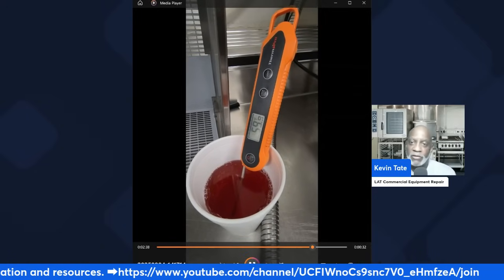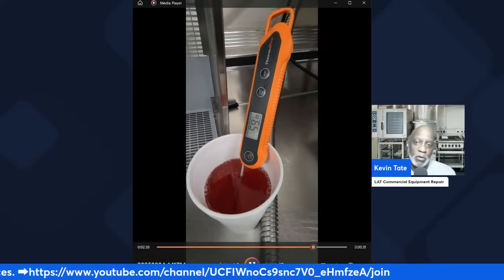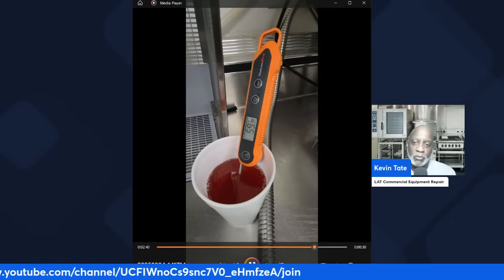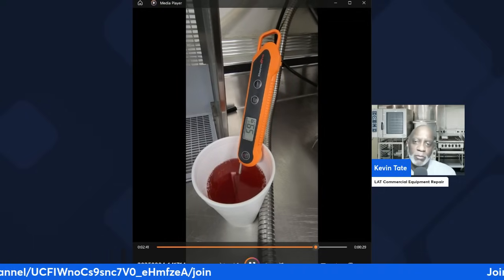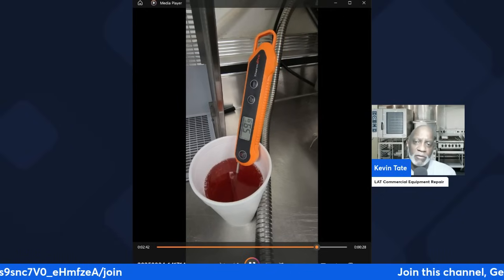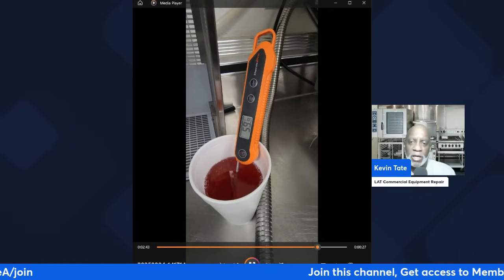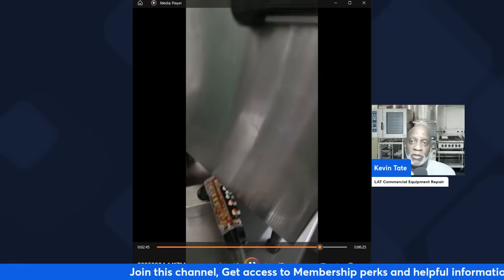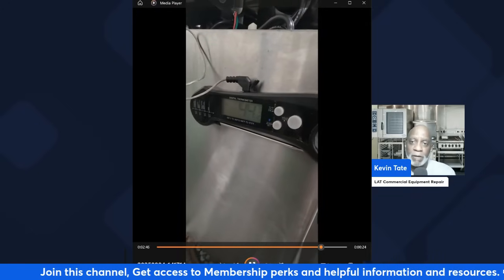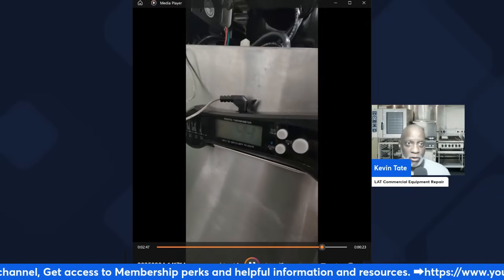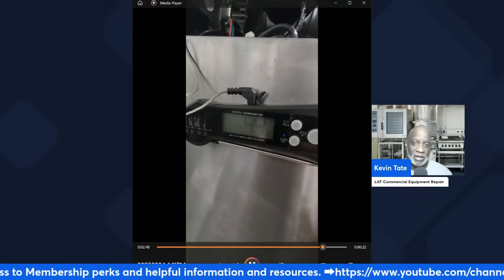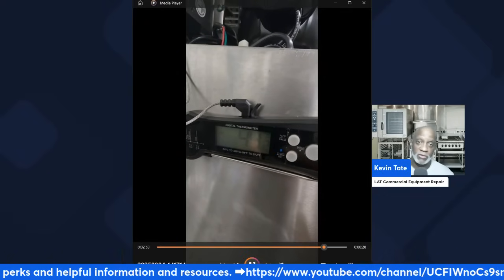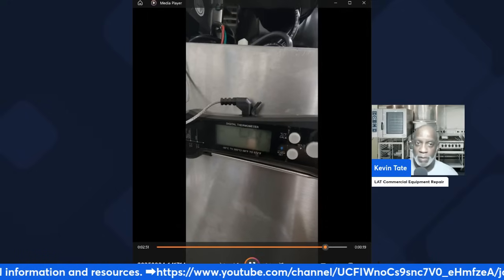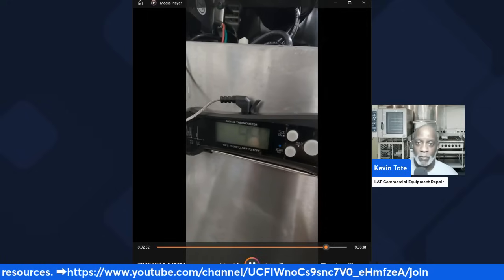I just test the temperature to see if it's going down. This one was sitting for a little bit, but it's giving me a reading of like 59, and the tank is still freezing down. Now we're at 44 degrees, so I'm just letting it go down gradually. Still, this is a good test for checking out the chiller.